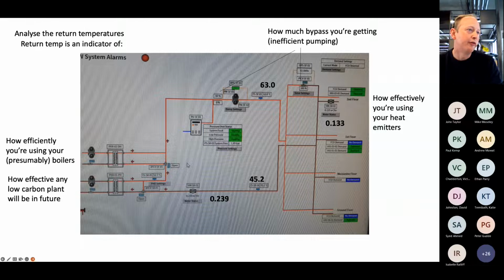And that's appropriate for VRF systems, that's appropriate for air source heat pumps or ground source or whatever you want to do. It's appropriate for boilers. It's true across the board. You can see that this site isn't working desperately right, and it's to do with an imbalance of flow, and you can see that there's a bypass. It's actually bypassing too much water and mixing relative to what's coming back from the fan coils.